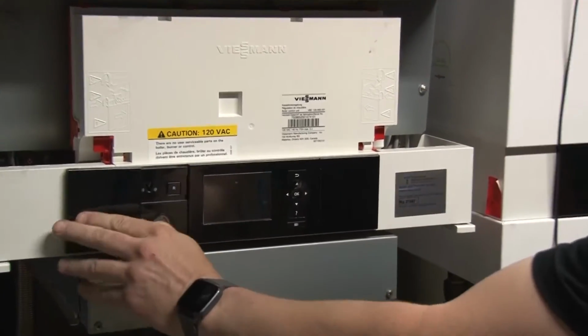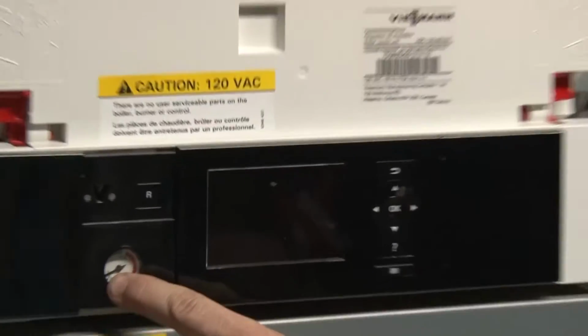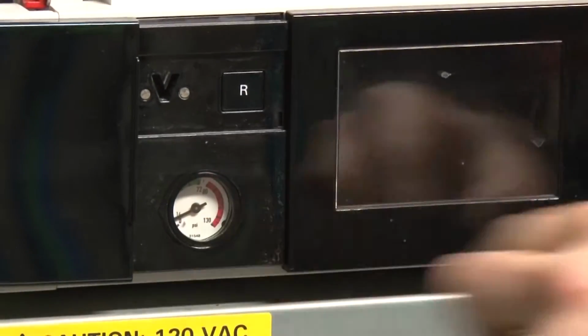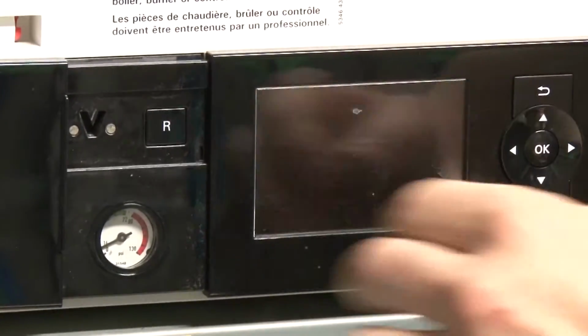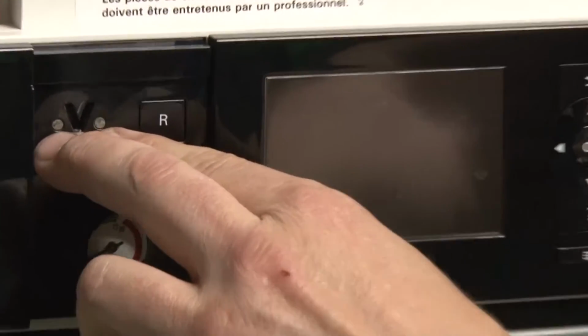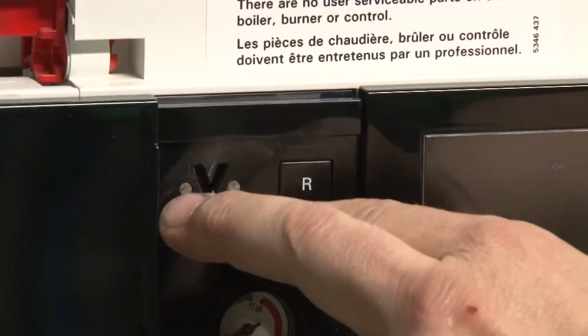On this side, you've got your pressure gauge on the bottom. We always want to see that kind of around the green area of the pressure. Your reset button for lockouts. If you have a combustion control lockout, there's your reset button. And of course, you've got what we call OptoLink in the Viessmann term. Those are just lights basically.